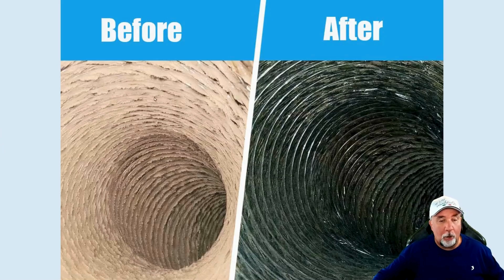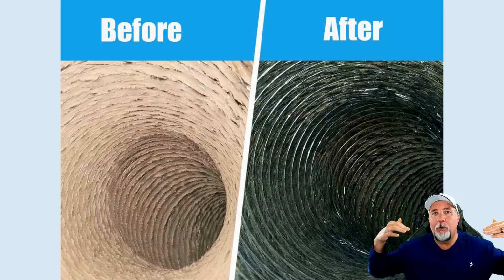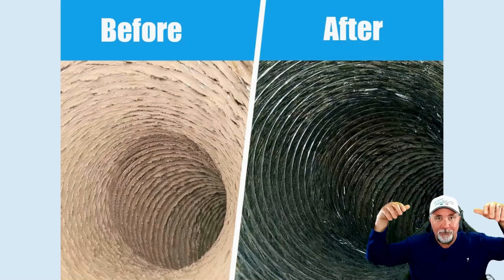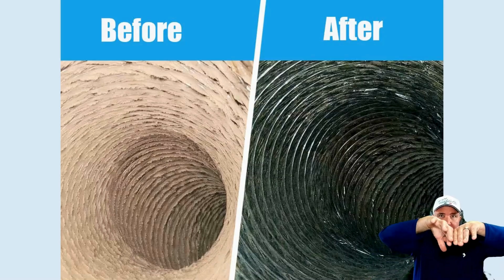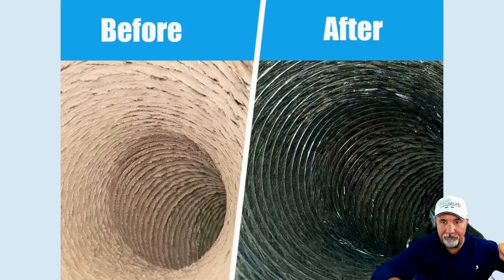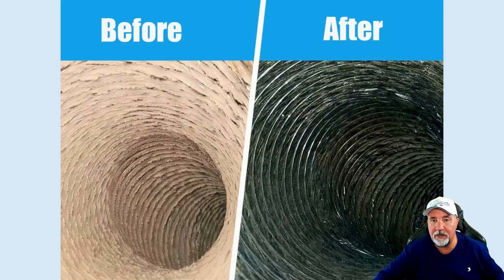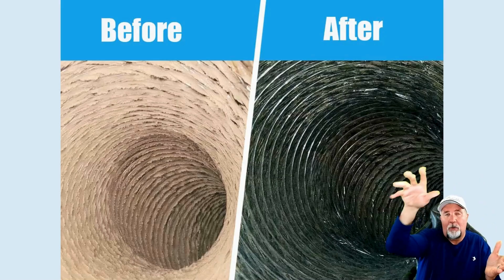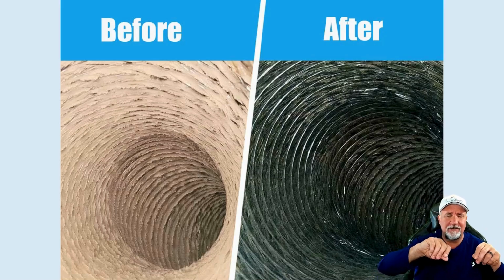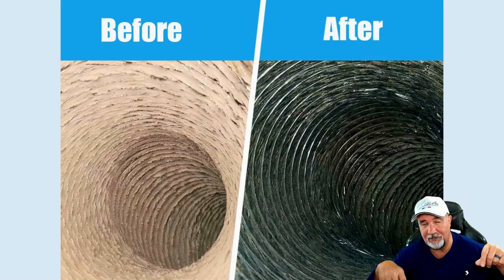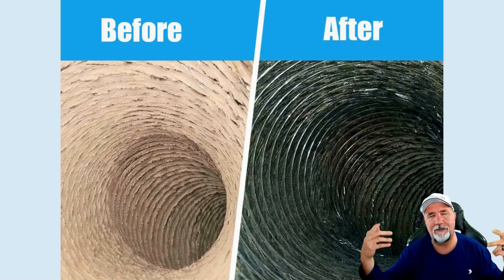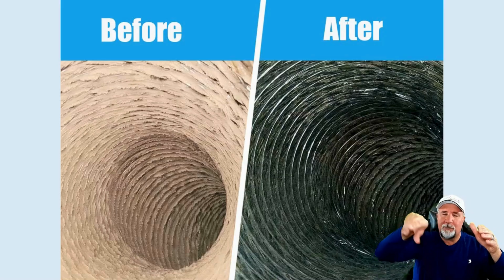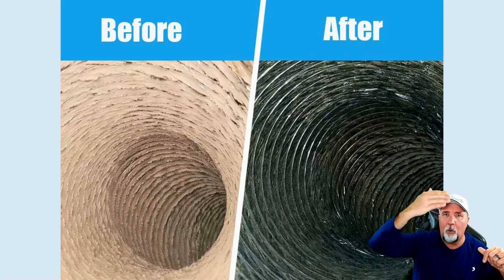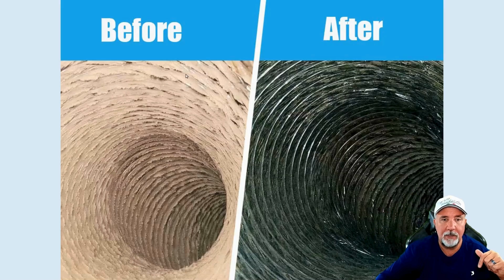So here is your dirty duct with all these particles. Now, these are rigid because you have this metal. It's like those round tunnels we used to crawl through as kids—that's basically what this is, with insulation around the outside. It's got a spiral wire that goes down the center; you can see it here. Then it has this material on the outside, kind of like a vinyl in some of them, though I'm not exactly sure what to call it—let's just use vinyl. It's plastic; I should have looked this up and prepared better, but hey, I'm not perfect. So it covers the spiral. What happens is, because of the spiral, air moves across it and dust and debris get caught up in those spirals—you can see how the dust collects as the air goes across.